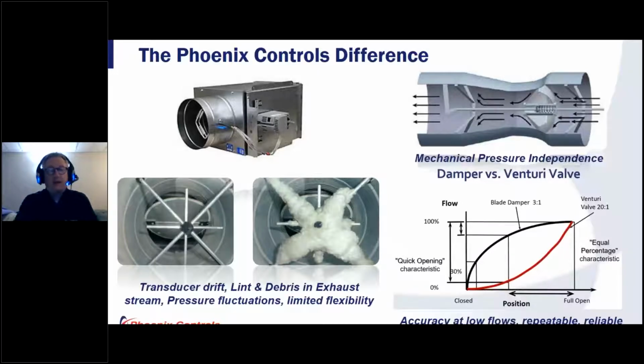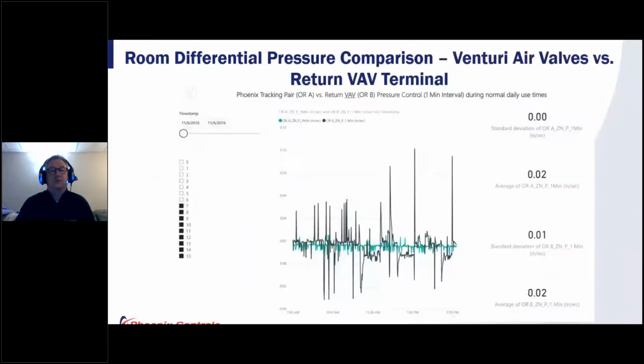And so it doesn't matter for the Venturi valve whether it's lower pressure, lower flow, or higher pressure, higher flow. We can maintain a high level of accuracy and dependability to maintain good directional flow during any occupancy state within that room. Again, offering that multi-use option for the hospital. And so this is what we do, right? We've been doing this for a long time. Again, this type of technology was needed on the research side, and now we're seeing that it's also needed on the healthcare side, and that's what we'll dig into.